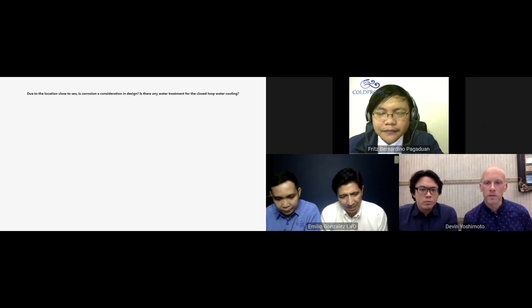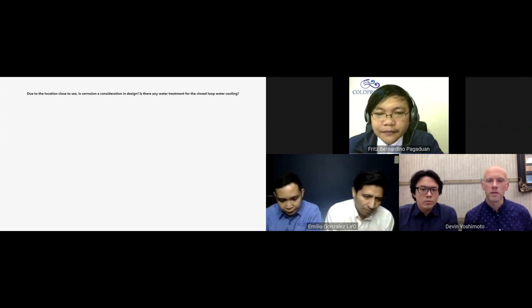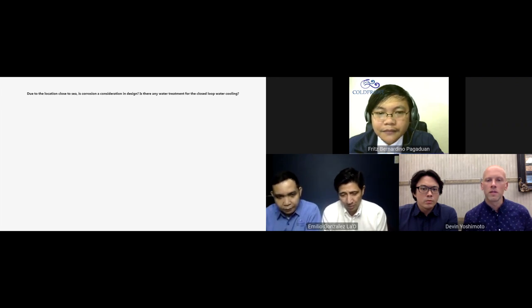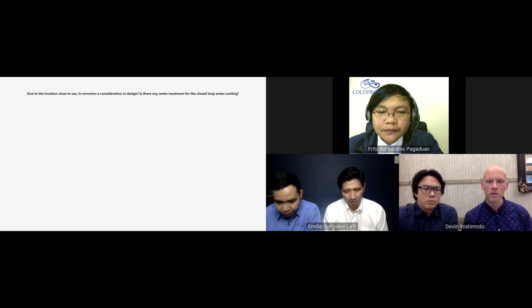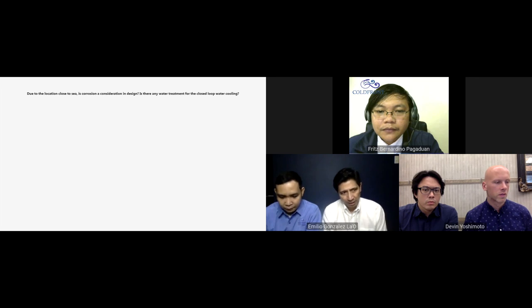Let me add real quick a little bit to that. As Fritz said, moisture is a big concern all over the Philippines just because of the high humidity here. As Fritz mentioned, we use aluminum piping. We use mineral water and glycol to ensure no foreign object or scaling happens inside. And then the dry coolers themselves are coated. They're called bluefin coated. Basically, there's a salt water proofing put onto the dry coolers so that they prevent corrosion and allow them to last a bit longer.